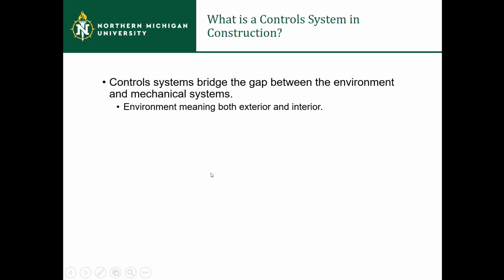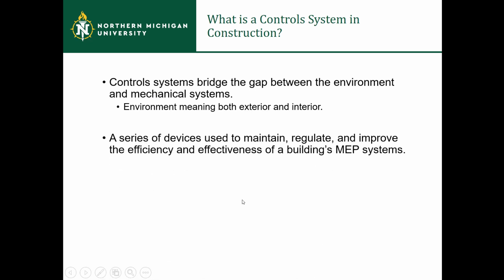Your control system is basically the brains of the operation. It bridges the gap between your environment and mechanical systems, meaning both exterior and interior environment. It's a series of devices that maintain, regulate, and improve efficiency and effectiveness of the building's MEP systems. I've had projects where point of sales, security, and other controllable items were added into that control system, all in one package deal. Historically and primarily we still only deal with MEPs when it comes to controls, but we can do a lot more. What we're trying to do is create efficiency and effectiveness throughout the entire building's operation, though that is the primary function.